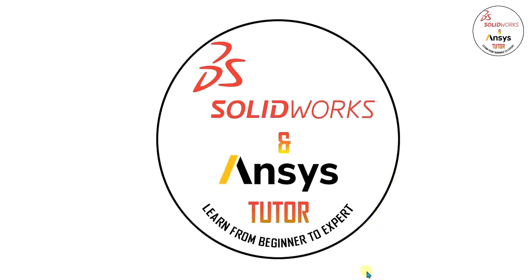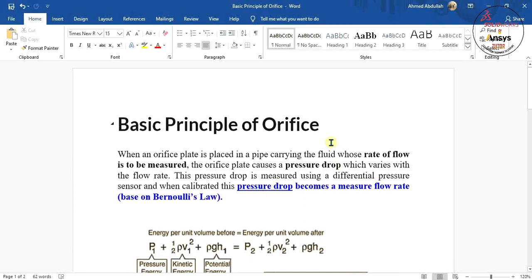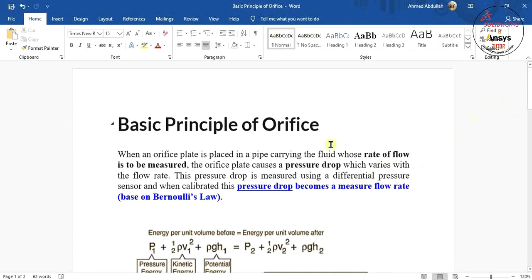First of all, we will see what is an orifice, what is the principle of orifice, and why we use it. When an orifice plate is placed in a pipe carrying a fluid whose rate of flow is to be measured, the orifice is used to measure the flow rate and to limit the pressure. The orifice plate causes a pressure drop which varies with the flow rate. This pressure drop is measured using a differential pressure sensor and when calibrated, this pressure drop becomes the measured flow rate. So we measure flow rate with the pressure drop.